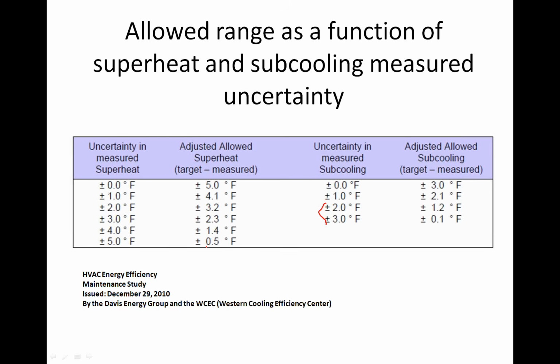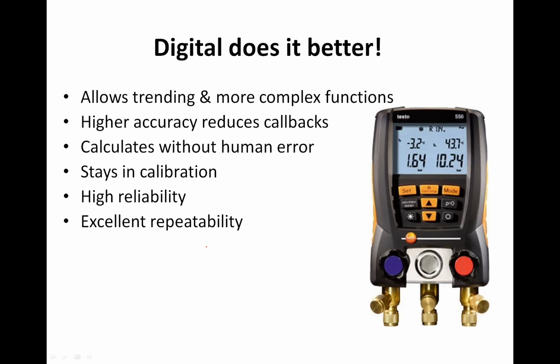And we've done the same thing with high efficiency equipment. We're selling somebody an 18-SEER piece of equipment today, and that equipment has to be set up exactly right to get 18 SEER out of it. If your airflow is off or your charge is off, you're going to start dropping off in performance. That's not what you're selling your consumer, and that's obviously not what we want to do when we're putting in new equipment. Simply, if you haven't considered digital, you need to look at it because it's going to reduce your callbacks and calculate without human error. We're going to stay in calibration, and we're going to increase our repeatability and reliability substantially.